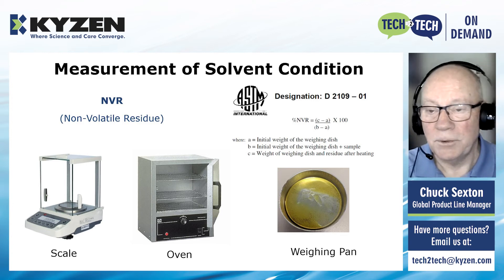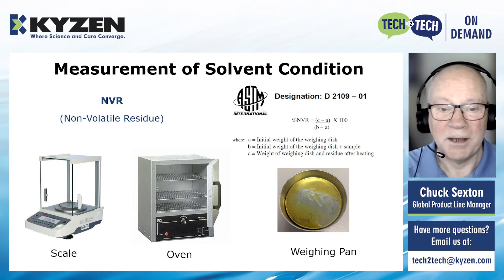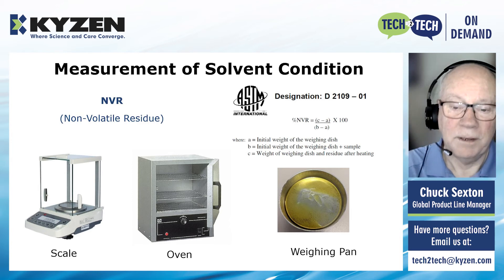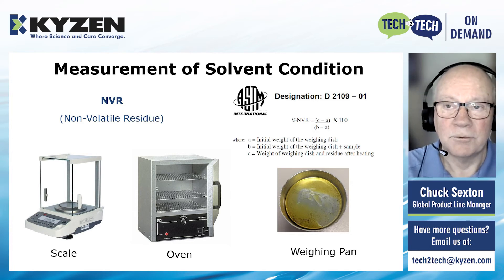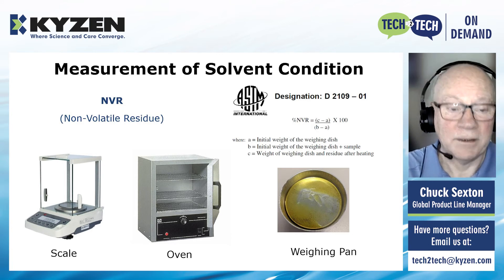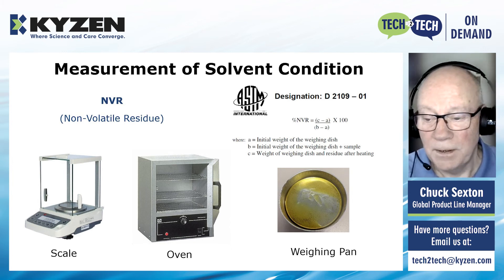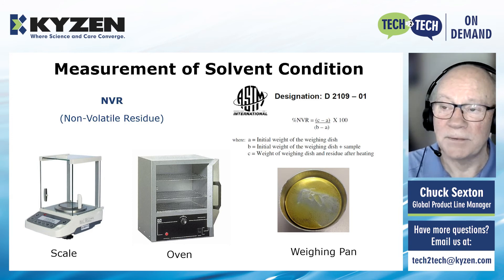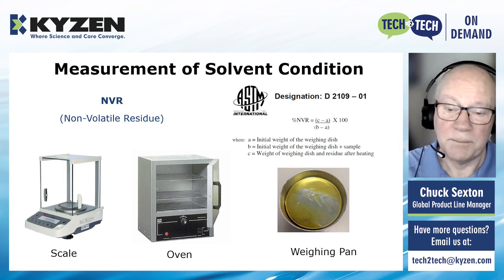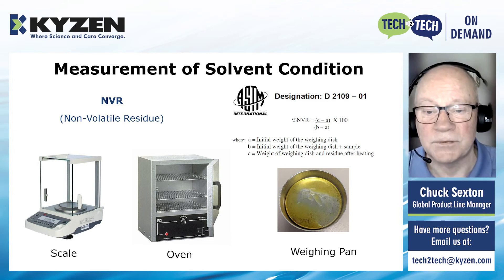I mentioned earlier that we do NVR — non-volatile residue — for both aqueous and for solvents. This is the tried and true ASTM method. It uses a laboratory scale and an oven where we measure the weight of the contaminant, drive off the volatile portion, and then weigh what's left — calculating the non-volatile residue. This is a really good measure of solvent condition and how close you are to end of bath. It works about 80% of the time; sometimes you reach steady state where concentration levels out but you're still cleaning.